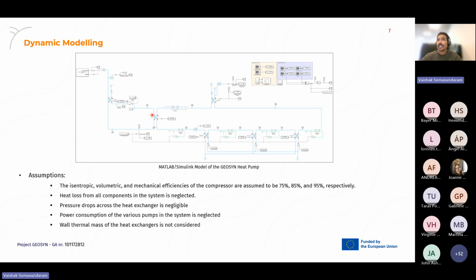I want to mention a few control strategies which we are using here. One is that we are modulating the speed of the compressor according to the required outlet sink temperature. In this specific case, it is 183 degrees centigrade. In addition, the opening of the expansion valve is modulated to control the superheat at the outlet of the evaporator. Further, there are 3 independent pumps which supply the cooling liquid to the intercooler, and the flow rate through the intercooler is also controlled so that we can have a definite superheat at the outlet of each stage of compression, and thereby we can limit the discharge temperature below 270 degrees centigrade.